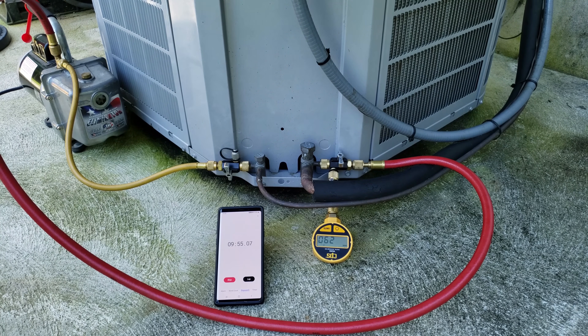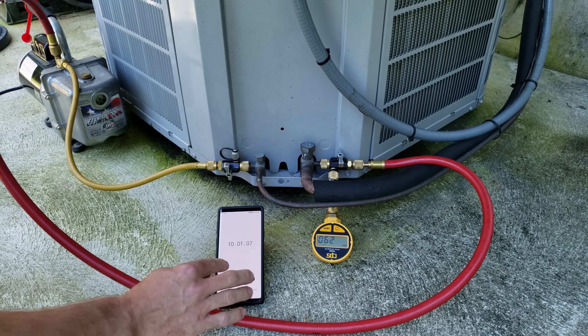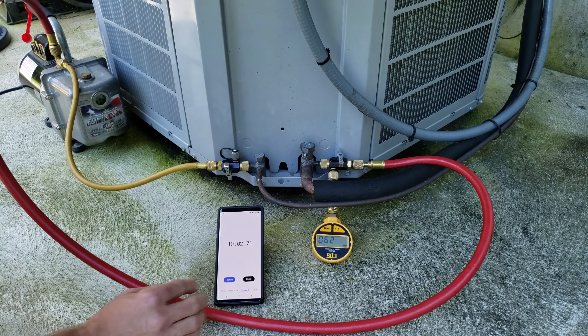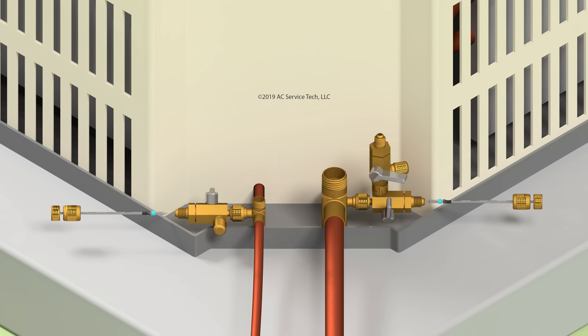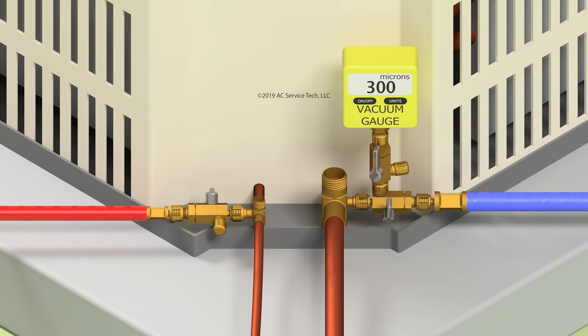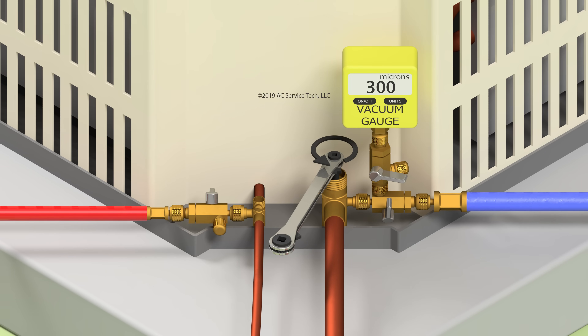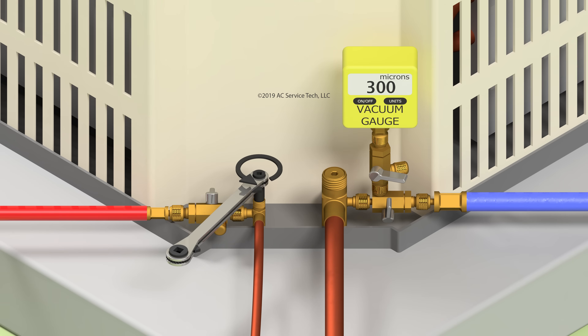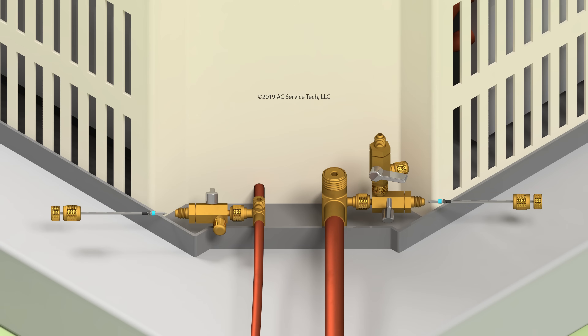One more thing I find a lot of people doing: after the vacuum and standing vacuum test, people are actually replacing the valve core before having a positive charge in the system. Don't do that. Make sure you put the valve cores in after breaking the vacuum with refrigerant. You can do that because you have the valve core removal tools attached to the ports — so you know for sure you still have a vacuum before you break it with refrigerant. If you don't do that, when you go to put those valve cores in, you're losing your vacuum and introducing humidity into that system.